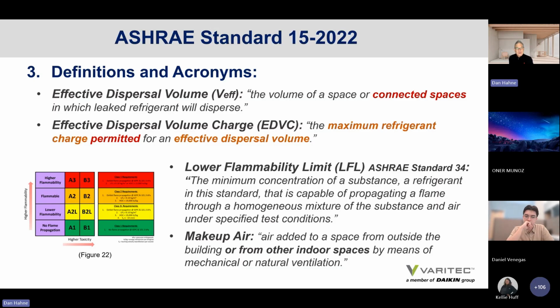It also uses the term effective dispersal volume charge, which is the maximum refrigerant charge permitted for an effective dispersal volume to fall within the refrigerant concentration limits called out in Standard 34. An understanding of lower flammability limit, which is the minimum concentration of a substance that is capable of propagating a flame through a homogeneous mixture of the substance, as it's the same definition as in Standard 34.